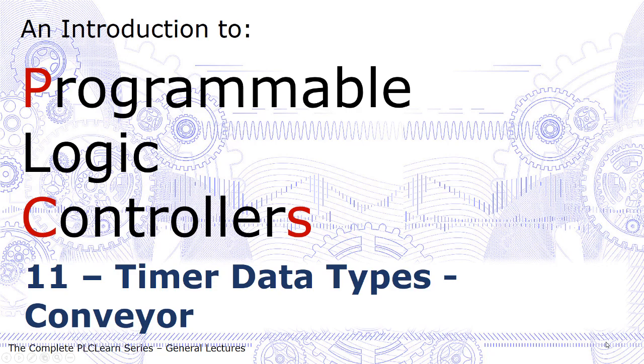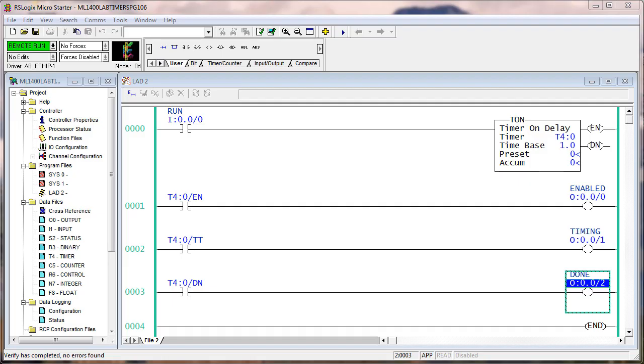Timer data types. The timer data type T4 colon zero is one element or one instance of the timer data type, and remember it's made up of three words: the control bits, the preset value, and the accumulate. In this particular lab it's not a practical application — it is simply set up to demonstrate how the timer data type executes when the rung is true.